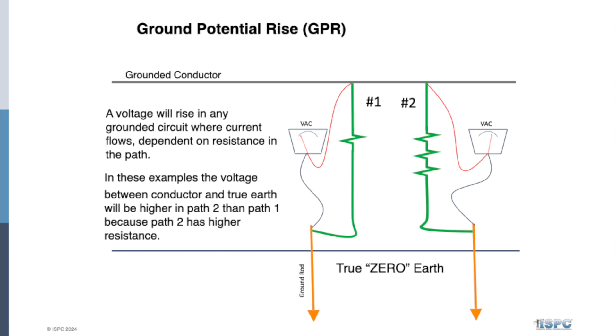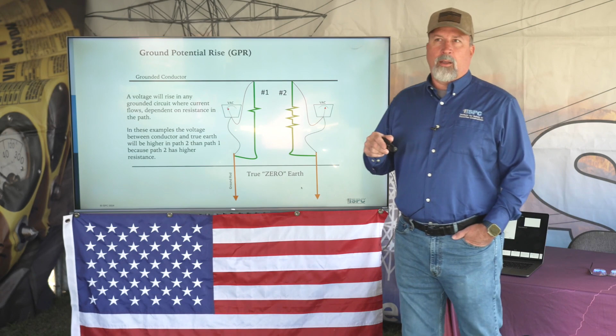You can see the resistance in ground number 2 is higher than the resistance in ground number 1, so you're going to have more voltage rise in that higher resistance ground. We need to understand that. If you become part of that one circuit, it might not be that bad. But if you get between these two grounds, that's where the potential difference comes in, and you can be injured. So these are things we need to understand about current flow—not only in normal in-service conductors, but in our grounding setups—where current will flow, what the potential is, and how we keep ourselves from becoming part of that circuit so we're not the ones who get injured.